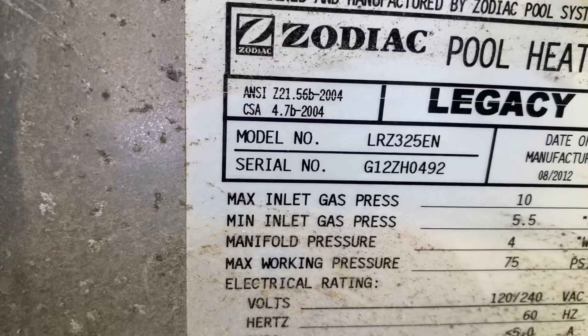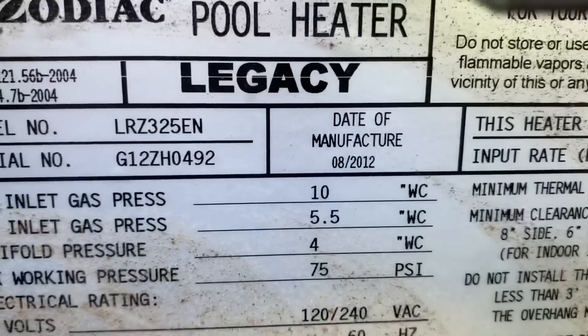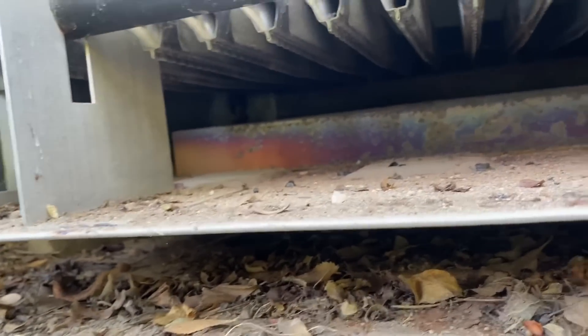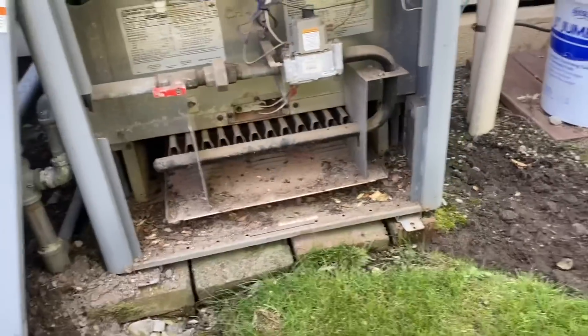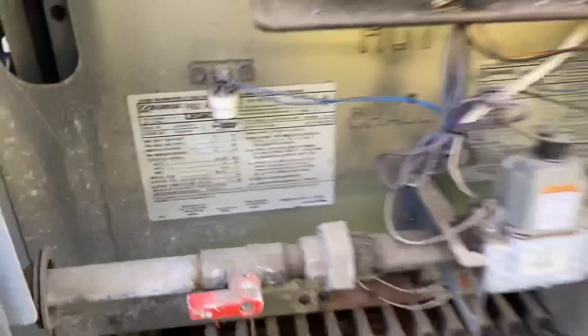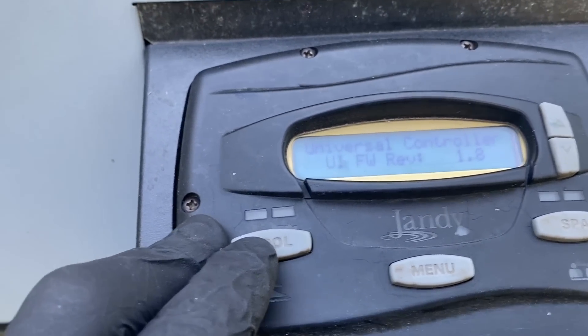One of the first things I look for is size — 325,000 BTUs. Date: August 2012. Then we look to see any corrosion or rust inside the combustion chamber. We have no rust — well, a little bit of rust back there. She needs a good cleaning, but considering it's exactly 10 years old, not too shabby. What I don't like is this controller not letting me do anything with it.